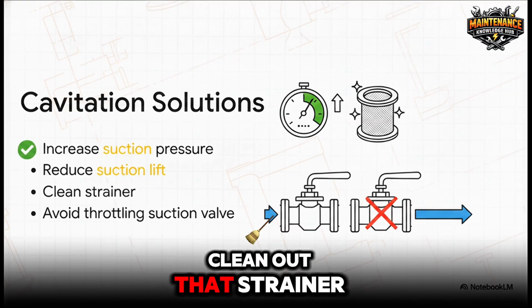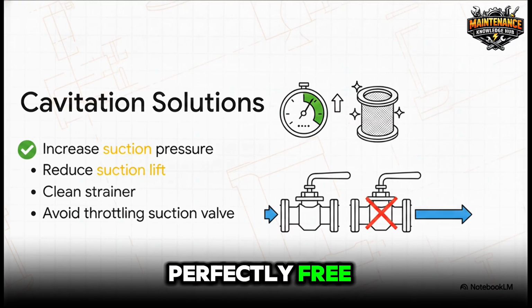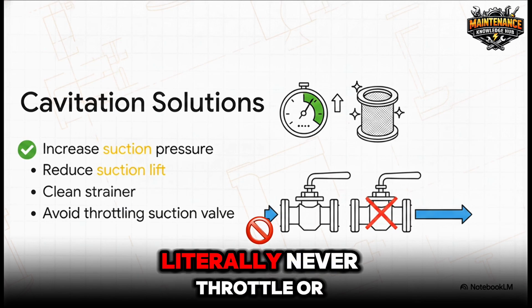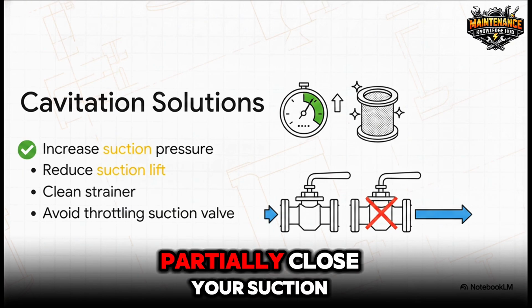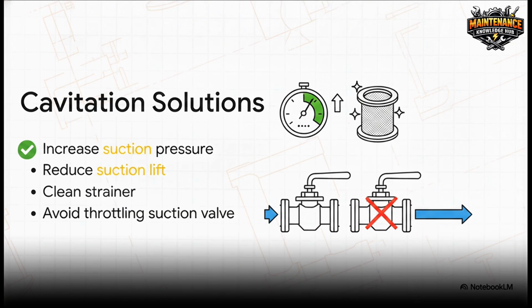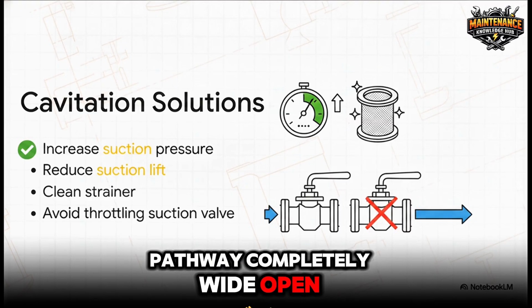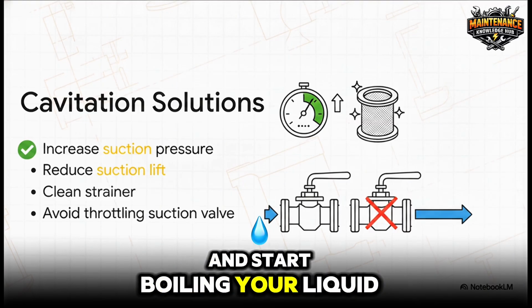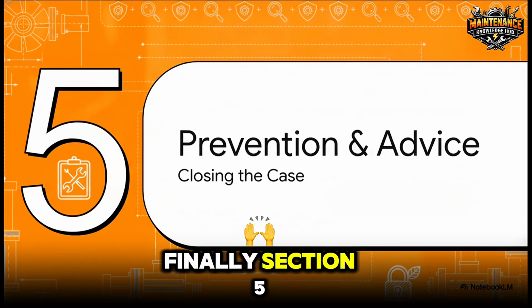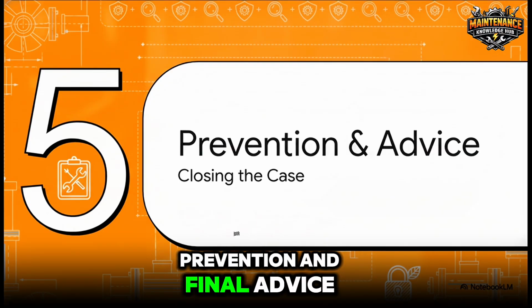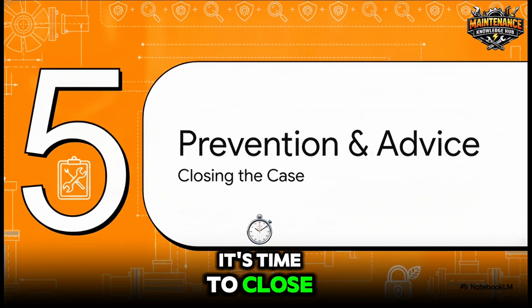Make sure you clean out that strainer so the fluid flows perfectly free. And this is a big one. Literally never throttle or partially close your suction valve, ever. You want that suction pathway completely wide open so the pressure doesn't drop too low and start boiling your liquid. Finally, section 5, prevention and final advice. It's time to close the case.